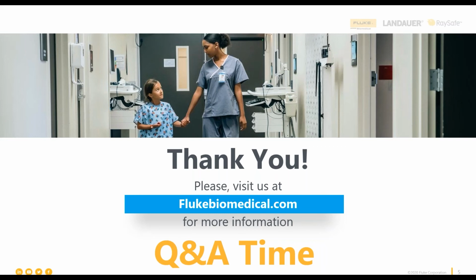Now, one of the things we didn't talk about in that video is that if you have your alarm limits for each parameter set in a normal way around a healthy patient or a typical patient, then when you go to hypertensive, it's going to exceed the high limit alarms and set off those alarms. Then normal should allow those alarms to quiet down, both visual and audible alarms. And when you go to hypotensive, it'll challenge the low limits for those alarms. So you're evaluating the alarms along with everything else. We didn't talk about that in the video, but that's exactly what happens.